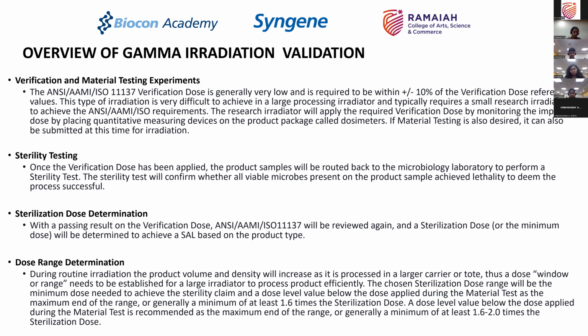What you've done so far is at a lab scale, in a controlled environment, in a very limited space. Now, when you're trying to do this at a large scale, you cannot just stick to the minimum dose, because if you stick to the minimum dose, there could be certain shadow areas within the irradiator, and therefore your product might not get sterilized.